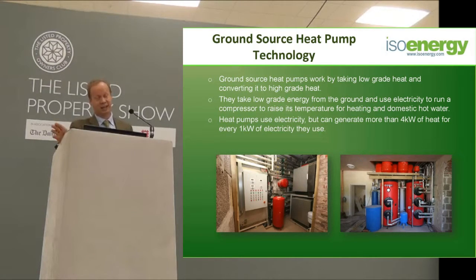If you own a care home, it's against the law to have 80 degrees going through the radiators — it's not allowed above 50. So it is very easy for a ground source heat pump to deliver 50 degrees. And if we work on weather compensation, most of the time you'll find that a radiator designed for an 80-degree flow normally needs about 45 degrees going through it to maintain room temperature throughout winter. So there's a lot of opportunity here.